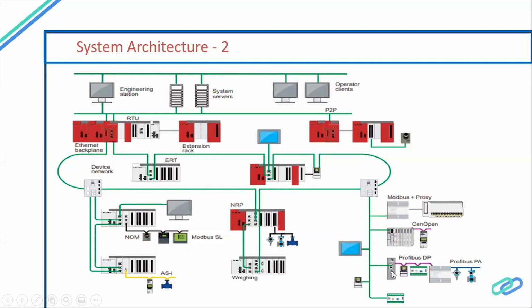And here you have Profibus connectors, Profibus PA and Profibus DP. In 90% of cases the PLC comes with Profibus DP only, so we need to use a DP to PA converter for Profibus PA. This is your Telemecanique controller, which is completely monitoring the motor protection device, directly connected to the motor over Ethernet. And there is one more protection device, connected on the CANopen protocol. So I am showing a different protocol here.